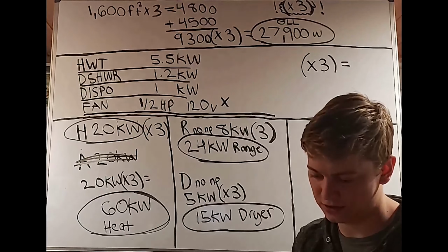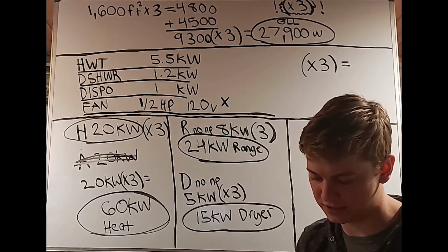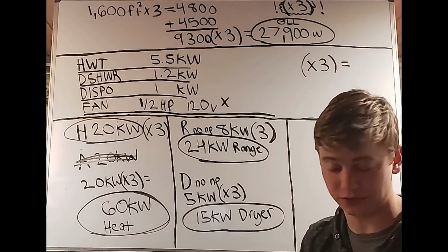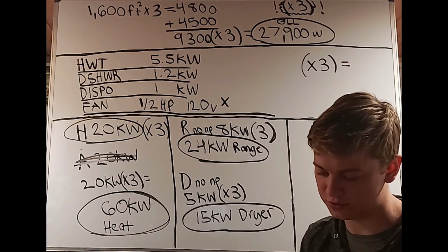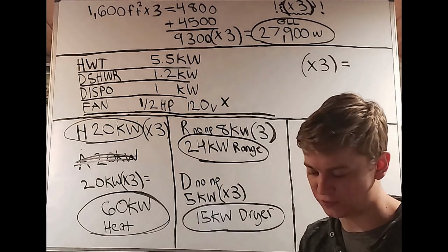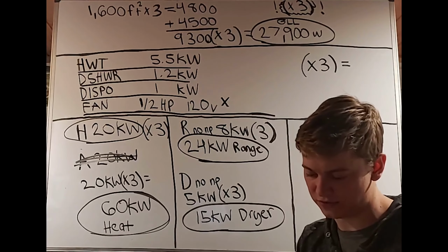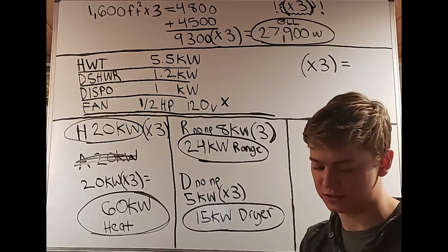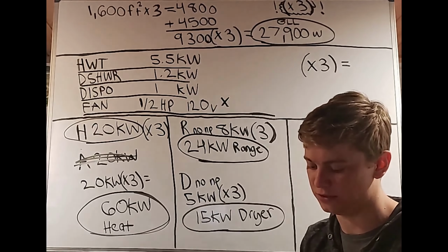We're going to go back into Article 220 in the very beginning, 220.5, subsection A, where it says voltages, and it tells you that we're going to use nominal voltages here for the load calculations. We see that we're only going to use the numbers 120, 240, 208, 347, 480, 277, 600, and those voltages will be used also in different combinations with each other, but you're only going to be using those.